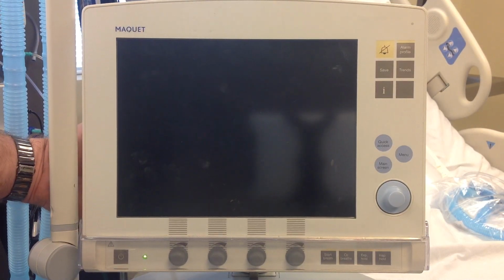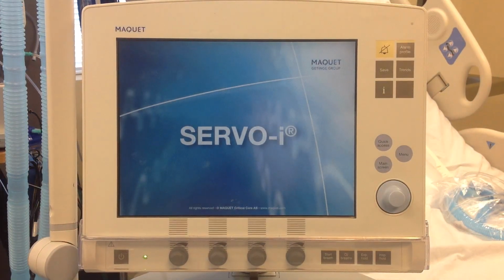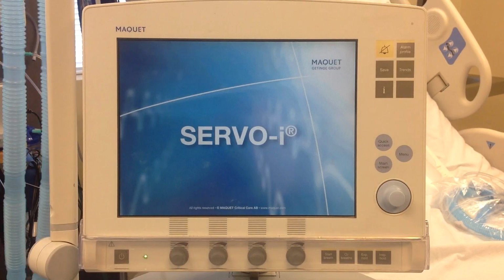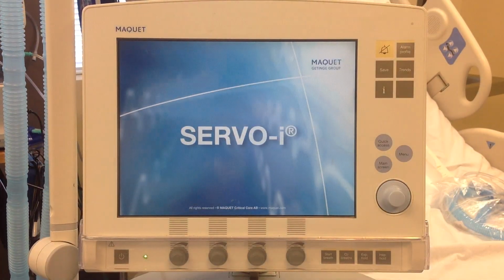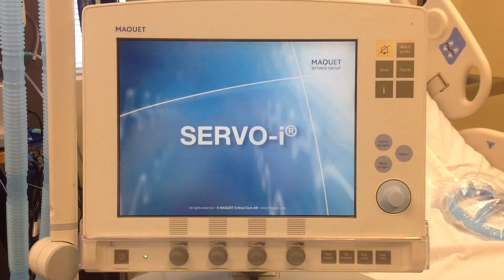Today we're going to work with the Servo I on doing the pre-use check and also setting the machine up in SIMV and assist control. First of all, we're going to do the pre-use check. I've already connected my high pressure hoses, my oxygen and my air to the wall, and the machine is plugged up to the wall.